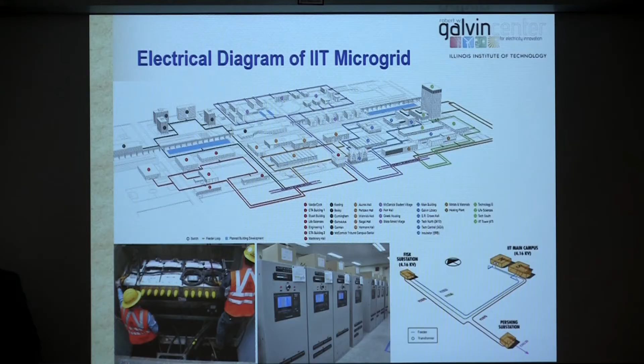We divided the campus into 7 loops, each self-sufficient, with major buildings connected to each loop. These 3 blue boxes represent the 3-phase switches I showed earlier. Each loop can individually be opened and closed, connected to either the south or north substation, and the 2 substations are connected through a normally open switch. So if there's a problem with one substation, the other can feed power to whatever was connected to the previous one.